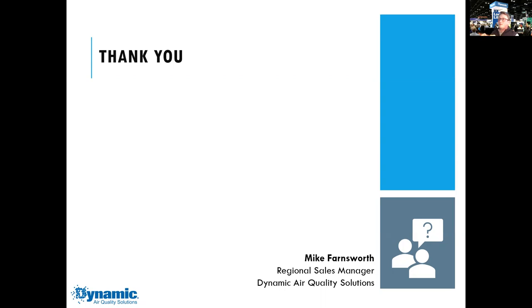So I typically recommend that if the equivalency aspect becomes a problem, just from the nomenclature of it, put in an actual MERV 13 filter. I don't know if I'd really speak to HEPA, but if you were to put a HEPA in the room, I would say don't put the extra MERV 13 in it. Use just the standard panel. If you have a HEPA, you're definitely more than covered, and that agglomeration aspect definitely helps improve your HEPA filtration. So it would be overkill to do a polarized media plus a MERV 13 filter plus a HEPA filter.